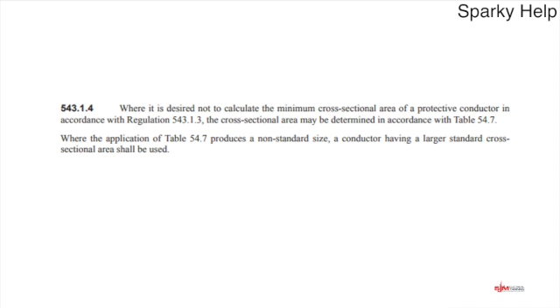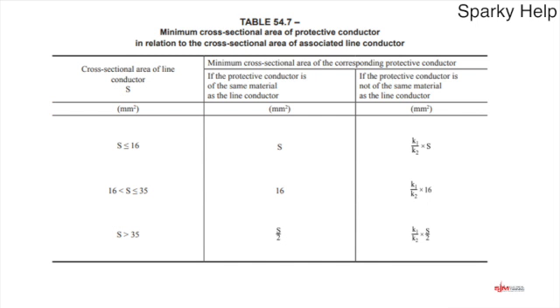Do they remember it comes from Table 54.7? Probably not, but it used to come from Table 54G. So what does this table actually say? Well, it hasn't changed in all the time that I've been looking at it. So Table 54.7, minimum cross-sectional area of a protective conductor. If we look at the first column, it says cross-sectional area of the line conductor. So your earth is sized against the line conductor. Remember, your line conductor will probably be the same size as your neutral conductor.